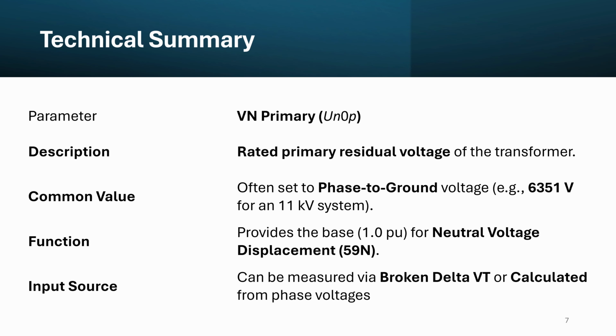Think of VT primary line to line as the speed limit sign on the road. It tells you the total capacity of the system. Think of the VN primary as a flood sensor on the shoulder of the road. The sensor needs to know the exact height of the curb, so it can tell you exactly when the water fault has overflooded the system.